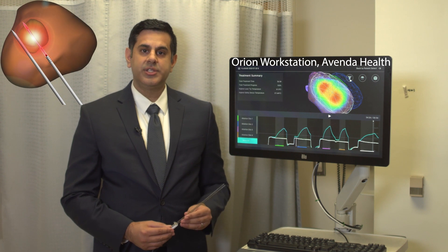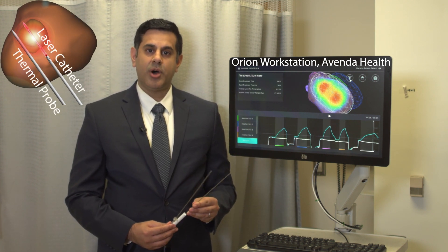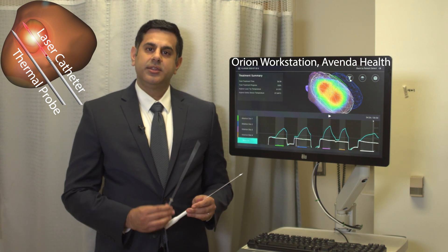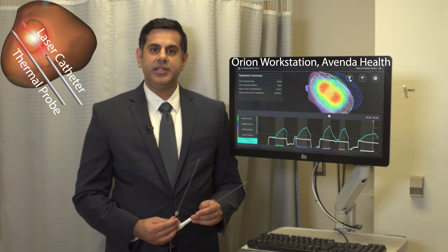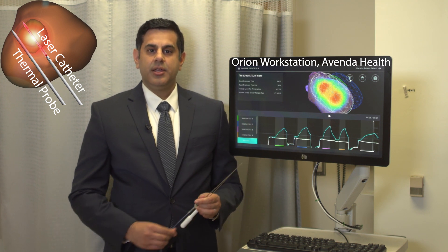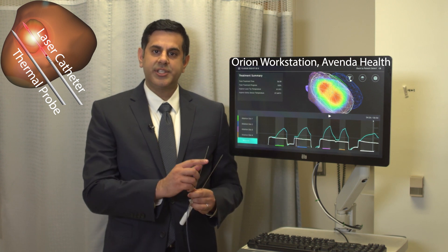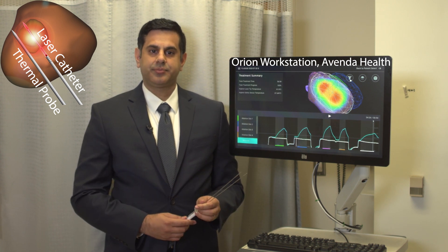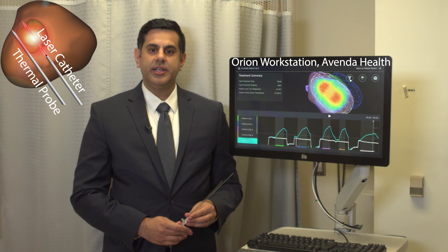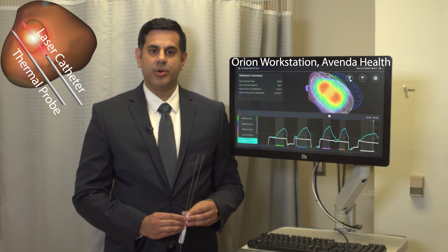The device includes a laser catheter, thermal sensor probe for tissue monitoring, and workstation. The laser catheter is a composite needle comprising of a diffusing laser fiber, a flow channel to circulate coolant, and ultrasound imaging markers.